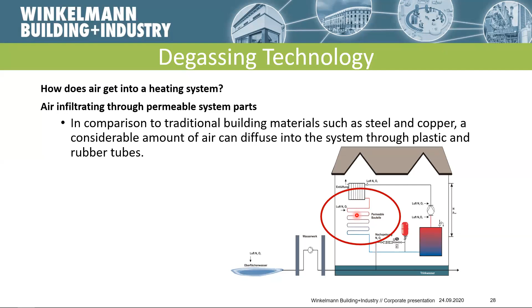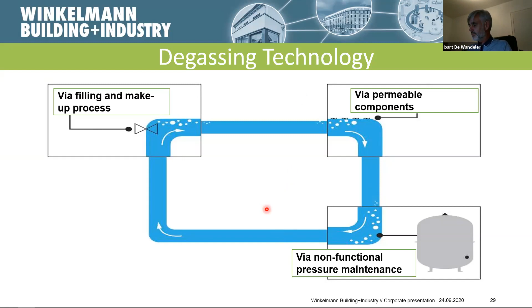This can also be through water makeup from the city, if you fill your system, or you need to create a water reserve for your expansion tanks, like I told one minute ago. Also for all plastic sealing, everything on the system. And of course, what's also important, if you have a vessel, certainly when you work with a static expansion vessel, and this vessel is not well calculated, if we have no water reserve below, then on the top of your system there will be a lot of sucking air that comes into the system through valves, to radiator valves, to even air separators. And that means you get a really high content of air in your system already.